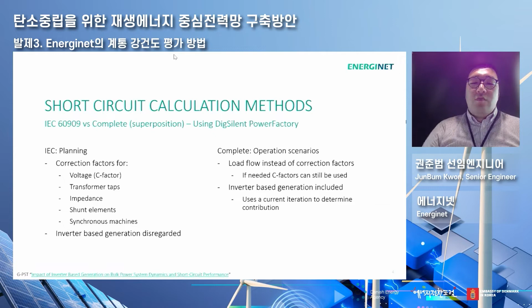And there's another way, the complete method. For each inverter, we come up with a load flow. So we have the operation scenario, and then we calculate the load flow instead of correction factors. Let me compare that. First, the short circuit current characteristic of conventional synchronous generators, where IP is the short circuit surge current, IK'' is the sub-transient short circuit current, and IK is the steady state short circuit current.